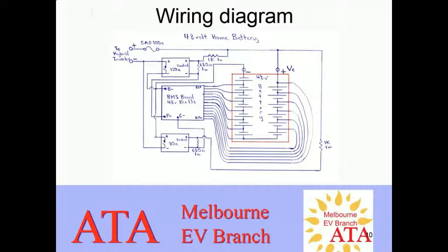This relay here is for charging — the charge relay. Control comes in through here and is controlled by the charge port on the BMS board. The power output board connection goes up to the relay at the top, the main output control relay that powers the unit. Wired this way, you then have a 48 volt battery capable of running 100 amps continuously.